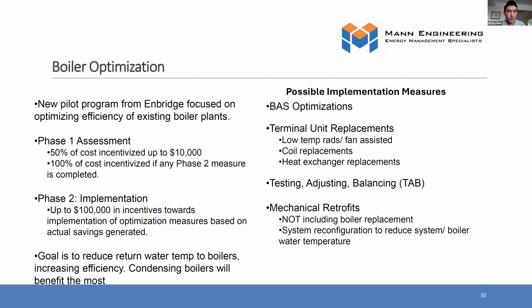Just a quick background on how condensing boilers actually work is, non-condensing boilers, for instance, the flue gases going out into the atmosphere are fairly hot. So all that heat is basically wasted because it's going out into the atmosphere. What a condensing boiler does is it extracts as much heat out of that combustion cycle as possible by actually condensing the flue gases. So the actual vent gases going out into the atmosphere are a much, much lower temperature, which means all that heat is actually going into the building instead of being wasted into the atmosphere. But the only way you can do that is if the water going into the boiler is cold enough to actually extract enough heat out of that system. So typically we want the water temperature to be less than 130, and the lower it is, like 90 degrees, I'm talking in Fahrenheit, or lower, you're going to get much closer to that 95 plus efficiency. So that's the goal here.